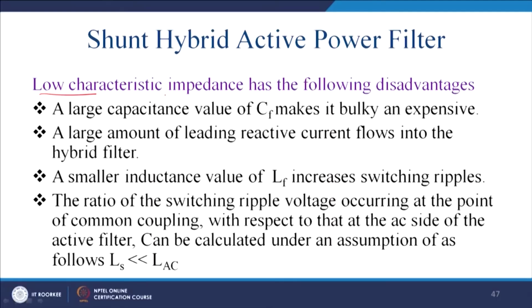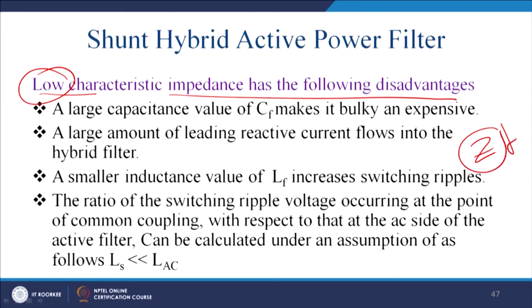Now, low characteristic impedance has the following disadvantages. If you have a low value of Z, then you will have the following disadvantages. A large capacitor CF, keeping the constant value of LF of course, makes the system bulky and expensive. A large amount of leading reactive power has to flow into the filter. So, the reactive power handling capability will also be governed by this CF value.